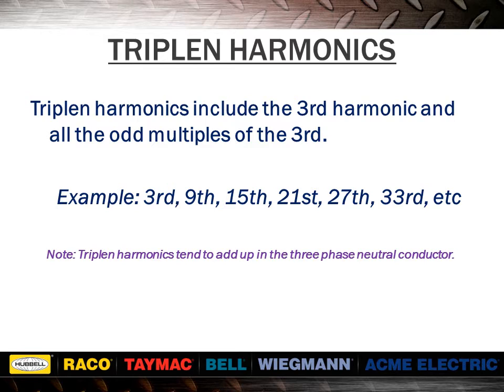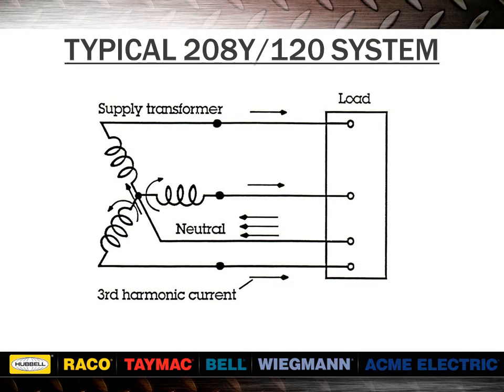It should be noted that triplen harmonics tend to add up in the three-phase neutral conductor. 60 Hz, or fundamental currents, tend to cancel in the three-phase neutral because of the 120-degree phase shift between adjacent phases. Triplin harmonics add up in the three-phase neutral because they are in phase with each other.